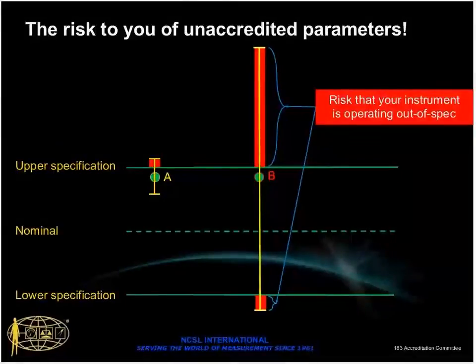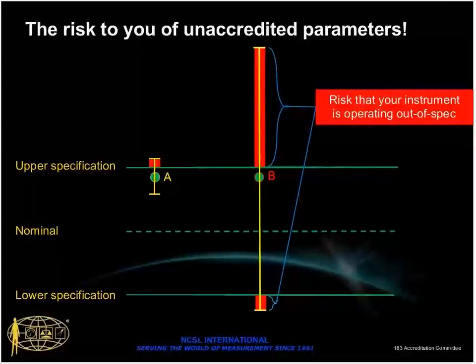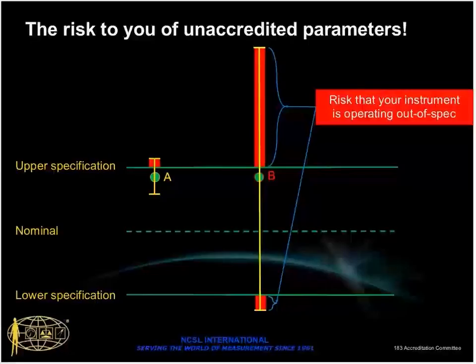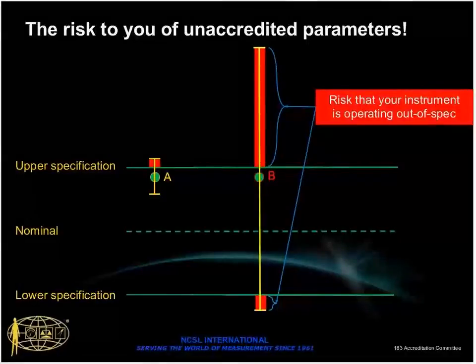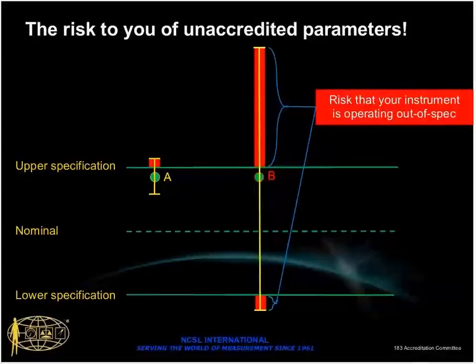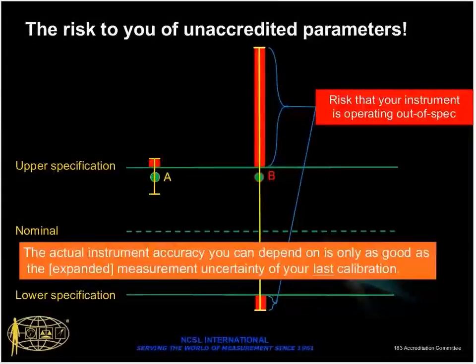Now, these can be identified with probability density functions and numerical integrals and all that kind of stuff. But you know what? You don't need to do one of those. You can look at this with your own eyeballs, and if this represents a probability distribution, there's a pretty good chance that on the right-hand side, the real performance of that instrument is that it's out of spec, and that would be true. So one takeaway from this is that the actual instrument accuracy that you can depend on when you get it back from the Cal Lab is really only as good as the expanded uncertainty interval from your last calibration.